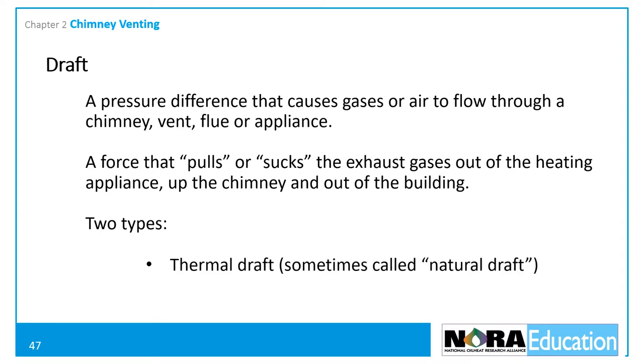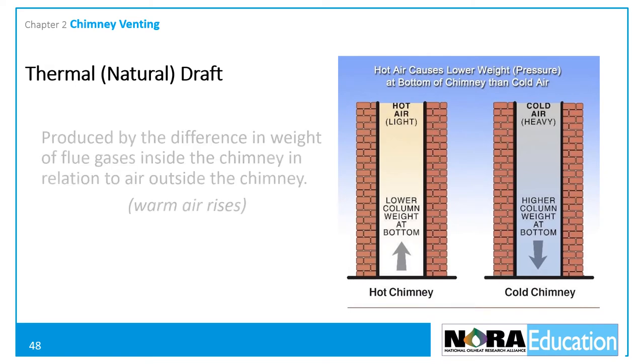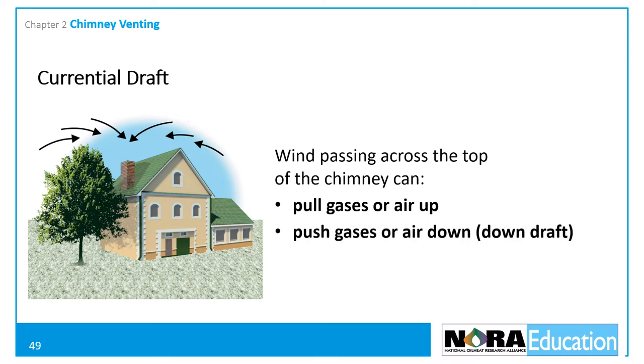Thermal draft, sometimes called natural draft, and currential draft. Thermal draft is produced by the difference in weight of a column of flue gases within a chimney or vent system, and a corresponding column of air of equal dimension outside the chimney or venting system. Currential draft occurs when wind passing across the top of a chimney creates suction and draws gases and/or air up. Currential draft can also cause downdrafts and push air down the chimney.